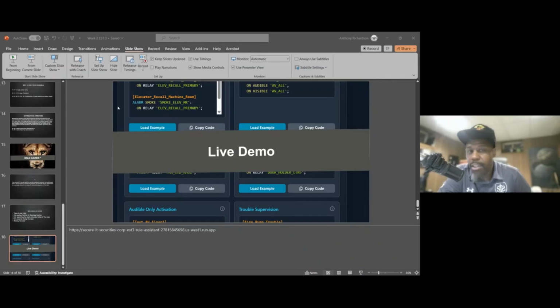And we have the duct detectors, which we could also write a rule for as well. So that rule will only activate this 1 smoke detector. It will not activate this smoke. So what I would generally have to do is, for this one here, I would probably put it elevator smoke, so I could write a separate rule. Because once I put the asterisk star here, this is going to be inside of that rule as well. I want this to work separately just to activate the elevators. I don't want this to work as the rest of these smoke detectors.